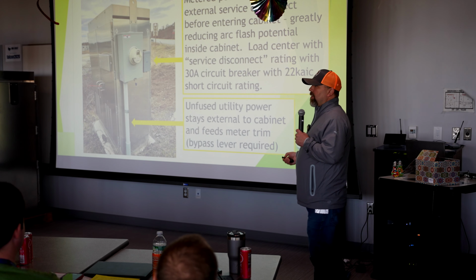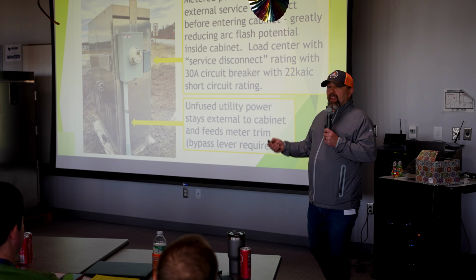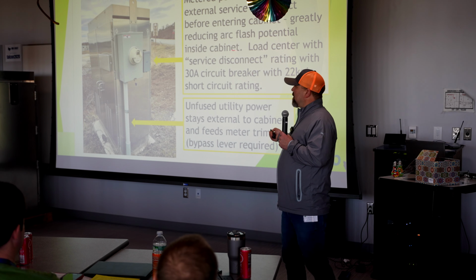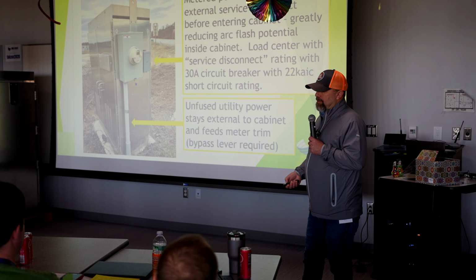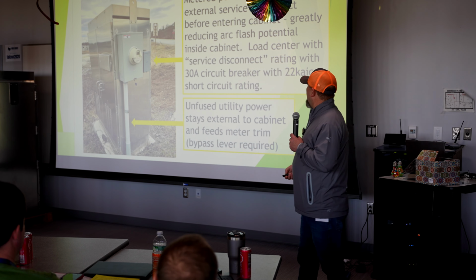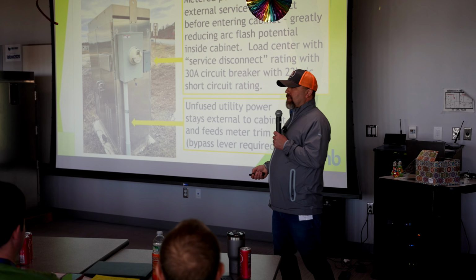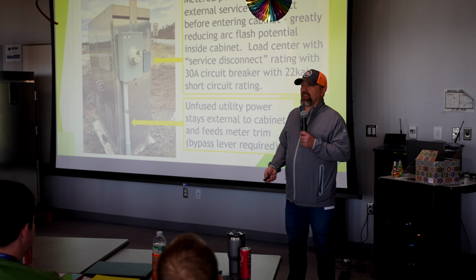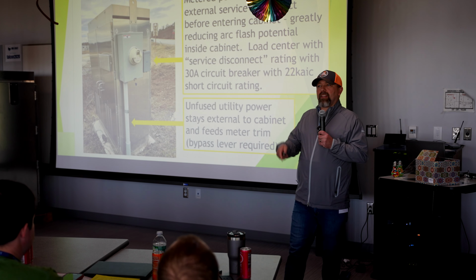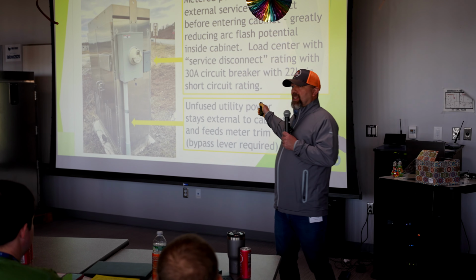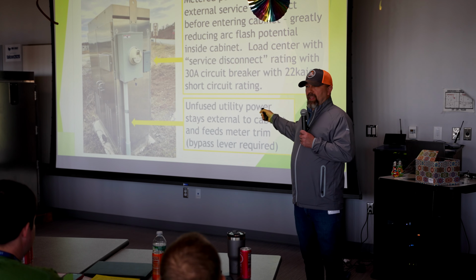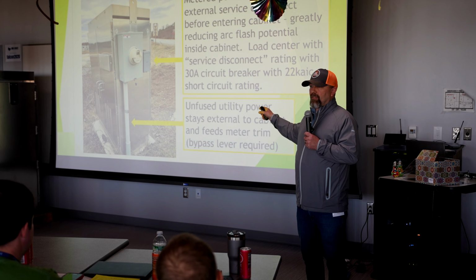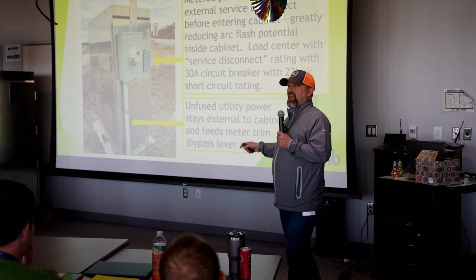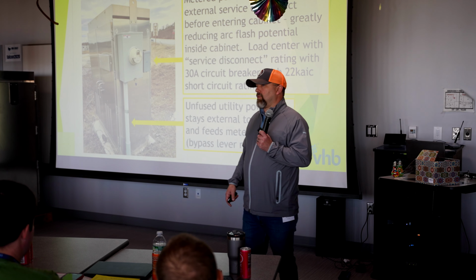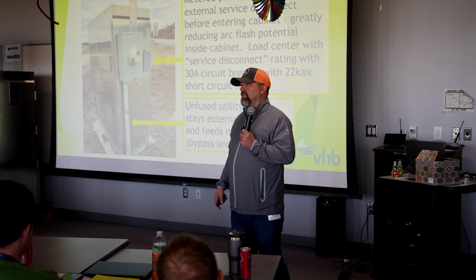It's pretty important to keep in mind that the breaker that's put in here actually has higher short circuit characteristics. Ron, maybe you could highlight this. I mean, that's been my standard practice. And I don't know if you necessarily need it for that breaker to act as a service disconnect. The breaker has to be bigger than the transformer feeding it.